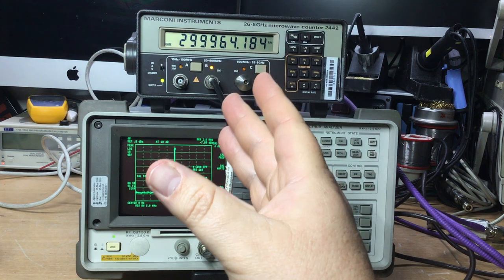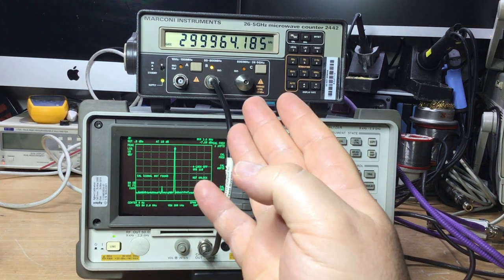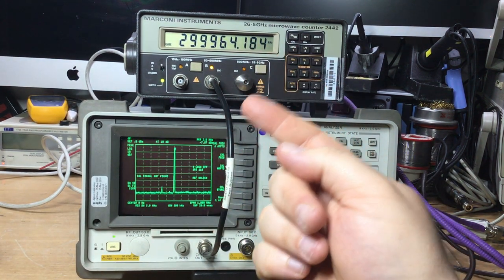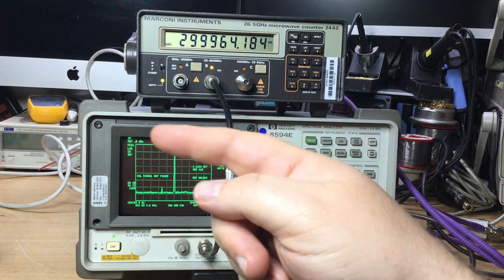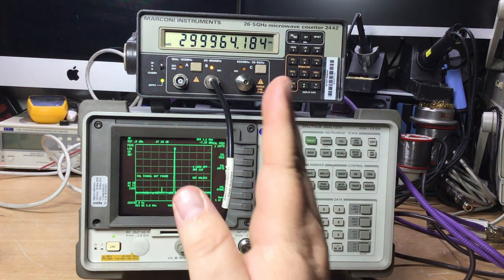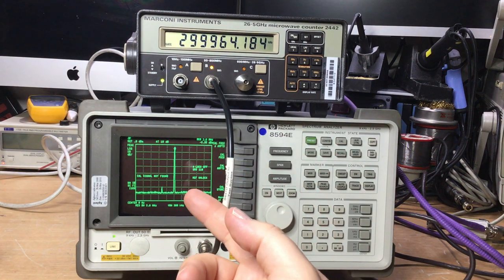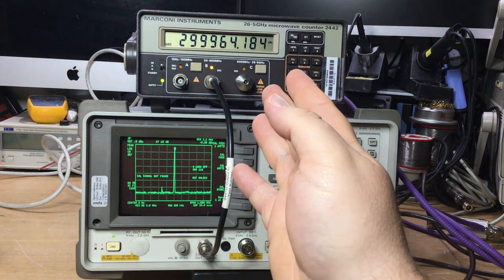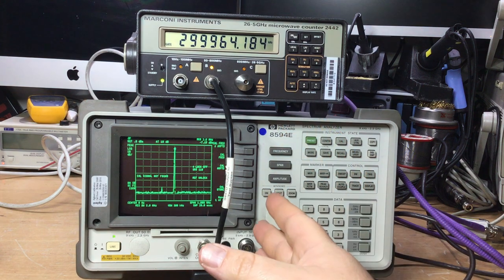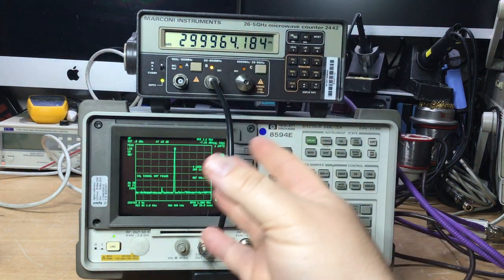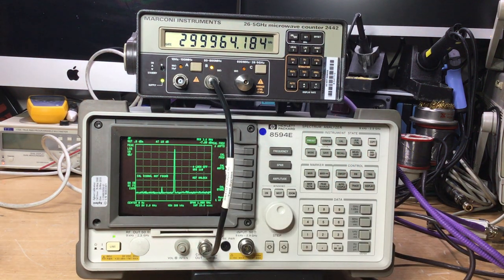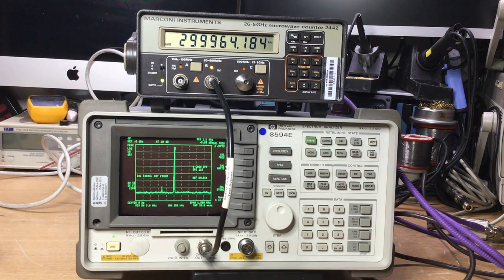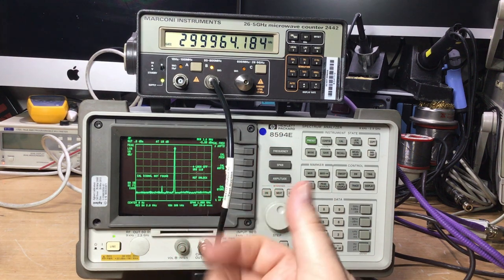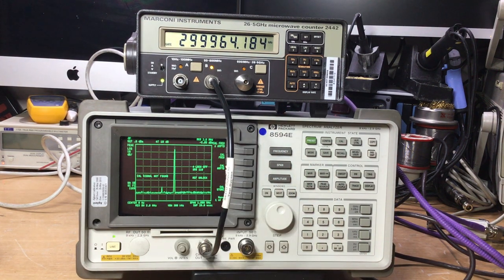But the thing is that with these, you're meant to leave them switched on for at least half an hour for the crystal oven to warm up, for the frequency stability of the frequency counter to settle before you take any measurements. So we've had this on for 30 minutes, just sat on top of this spectrum analyzer, just warming up, and obviously then it's reached its peak operating temperature. Now it's stable. Normally they reach stability quite quick, but I have a general rule of thumb, which is just leave them alone for a good half an hour to an hour maybe.